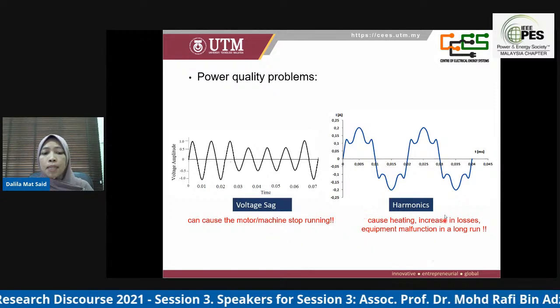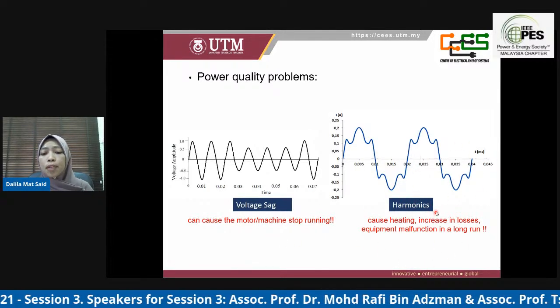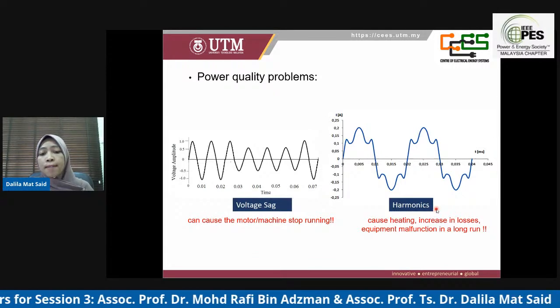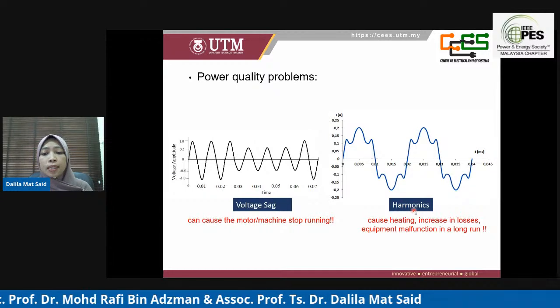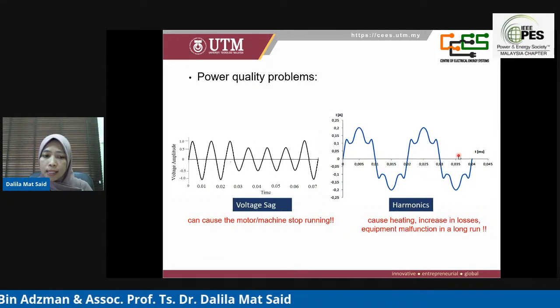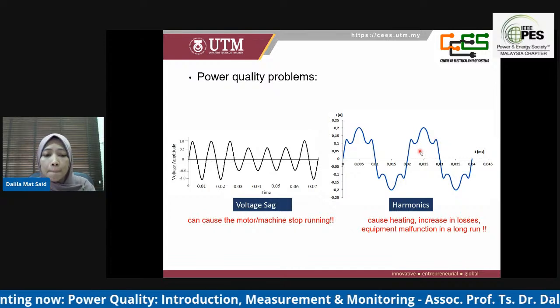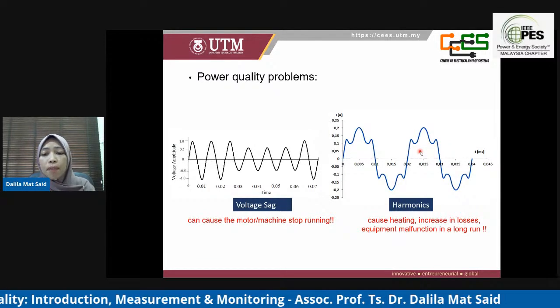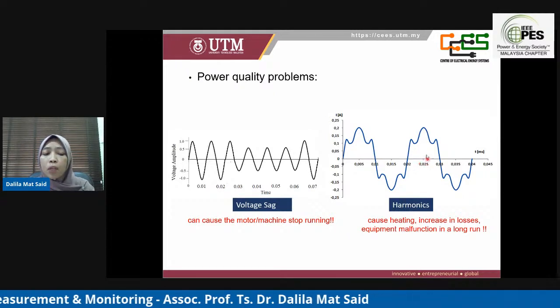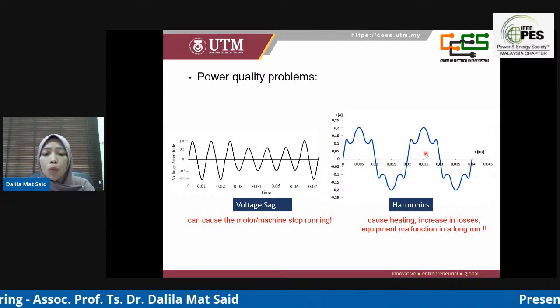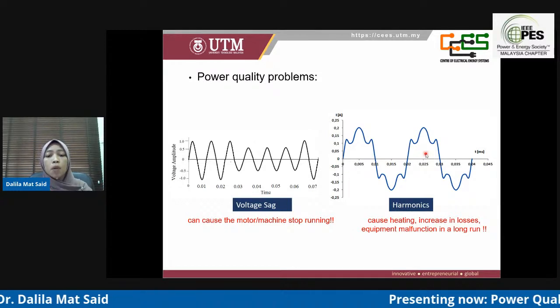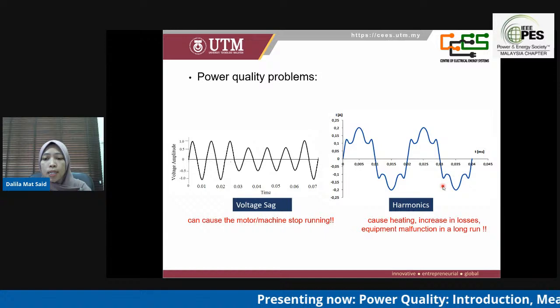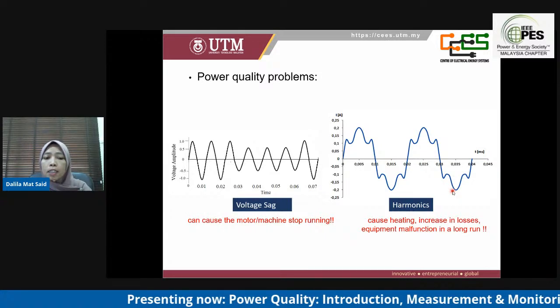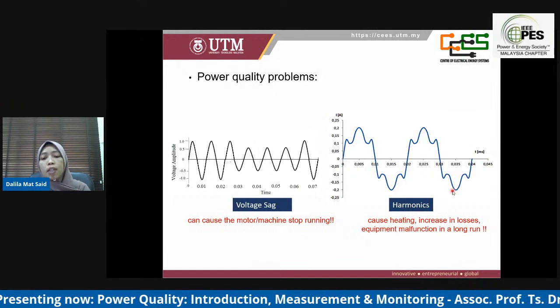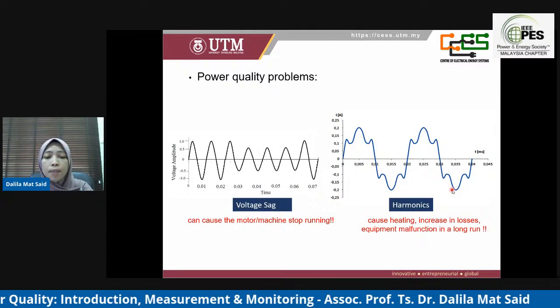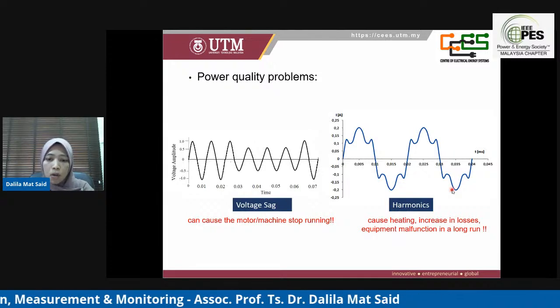The second problem, on the right side, is the harmonic. Harmonic, as we can see, is when the voltage or current waveform assumes a non-sinusoidal shape. They have distorted. The waveform corresponds to the sum of different sine waves with different magnitude and phase, having frequency that are multiples of the power system frequency. And the problem is caused by non-linear load connected to the system. The impact is increased probability in occurrence of resonance, neutral overload in the 3-phase system, and overheating in the cable or transformer.